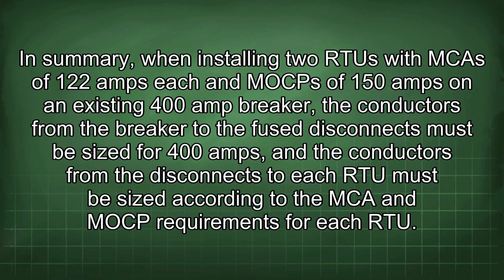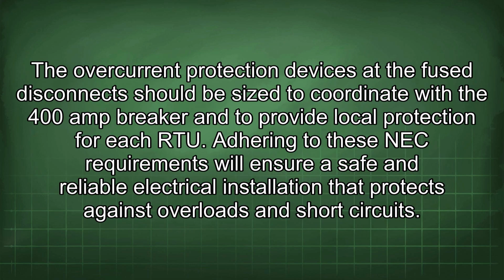In summary, when installing 2 RTU with MCA of 122 amps each and MOPs of 150 amps on an existing 400 amp breaker, the conductors from the breaker to the fuse disconnects must be sized for 400 amps, and the conductors from the disconnects to each RTU must be sized according to the MCA and MOP requirements for each RTU. The overcurrent protection devices at the fuse disconnect should be sized to coordinate with the 400 amp breaker and to provide local protection for each RTU.